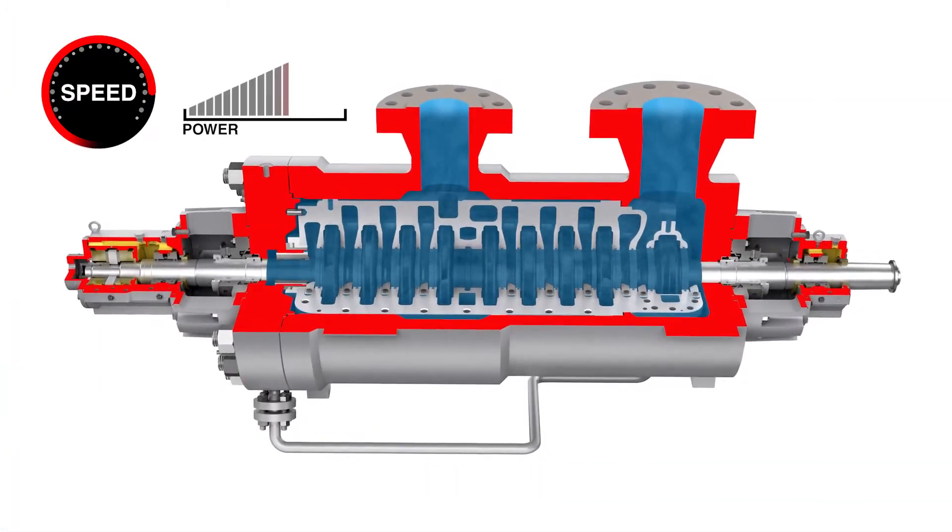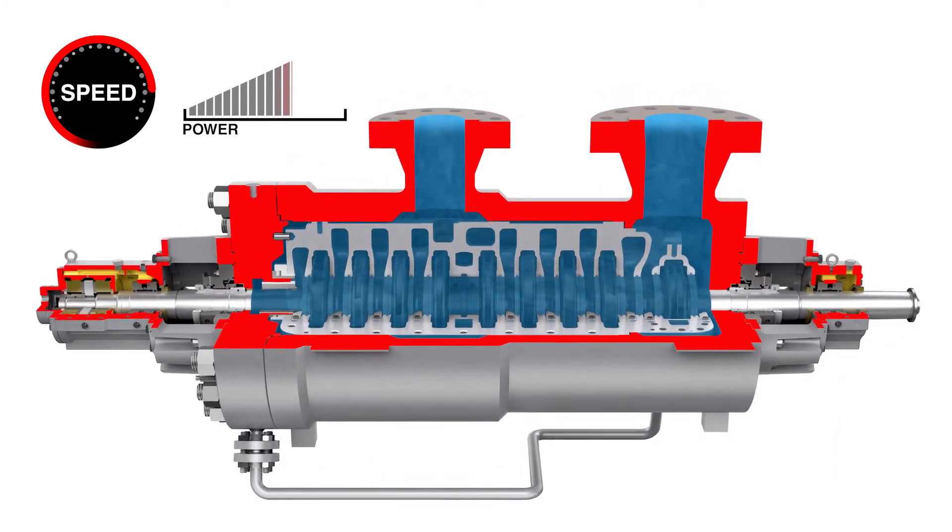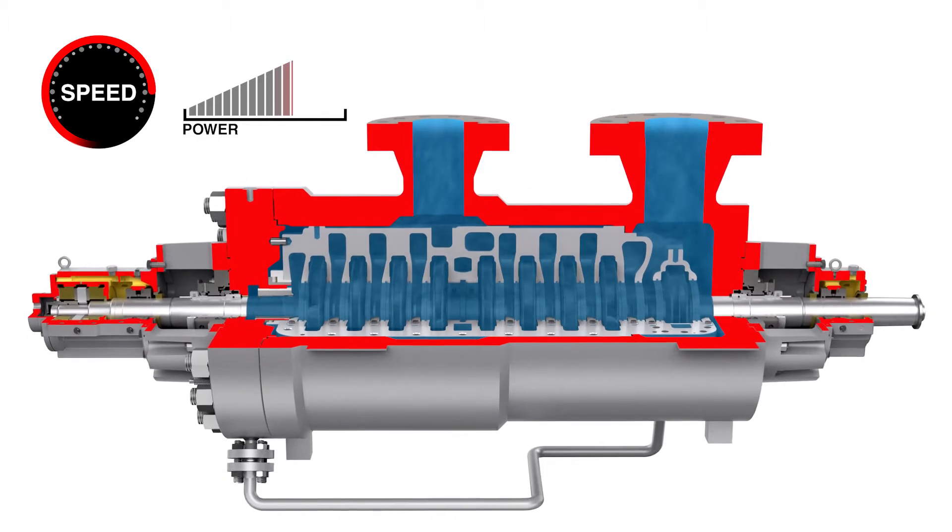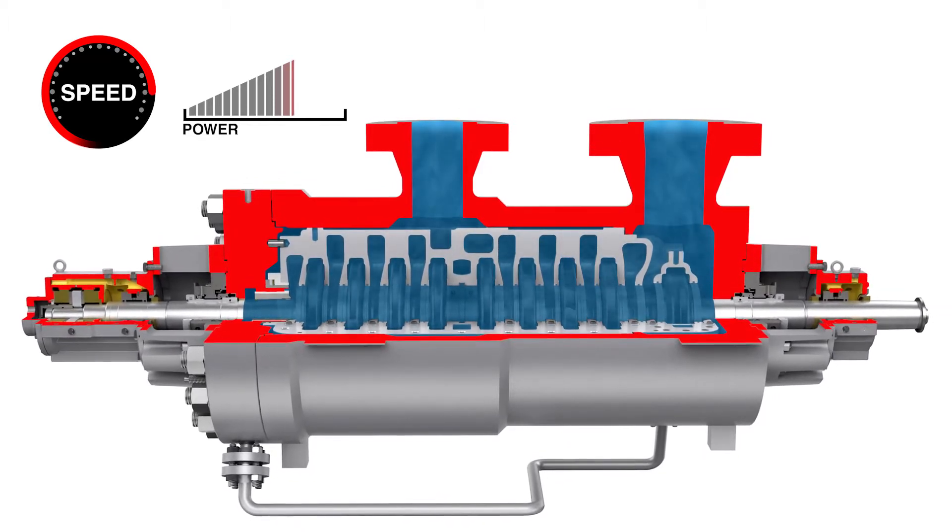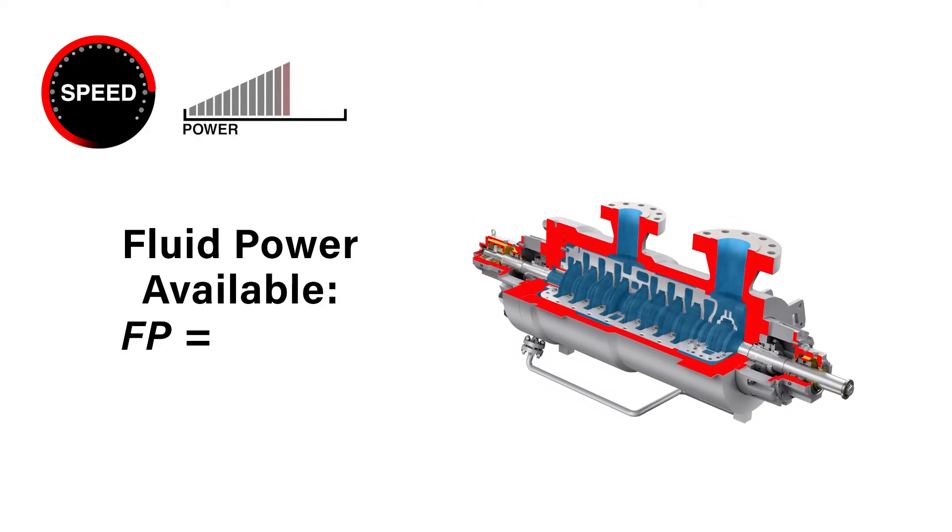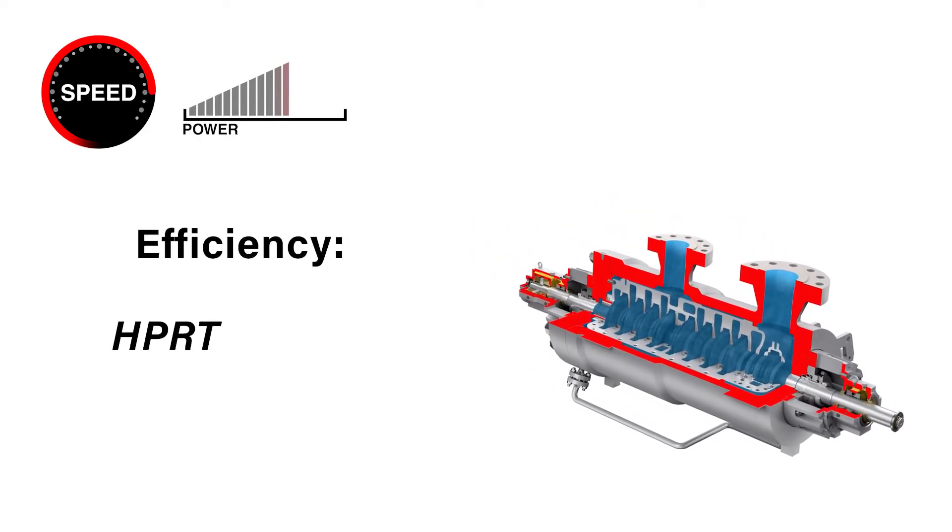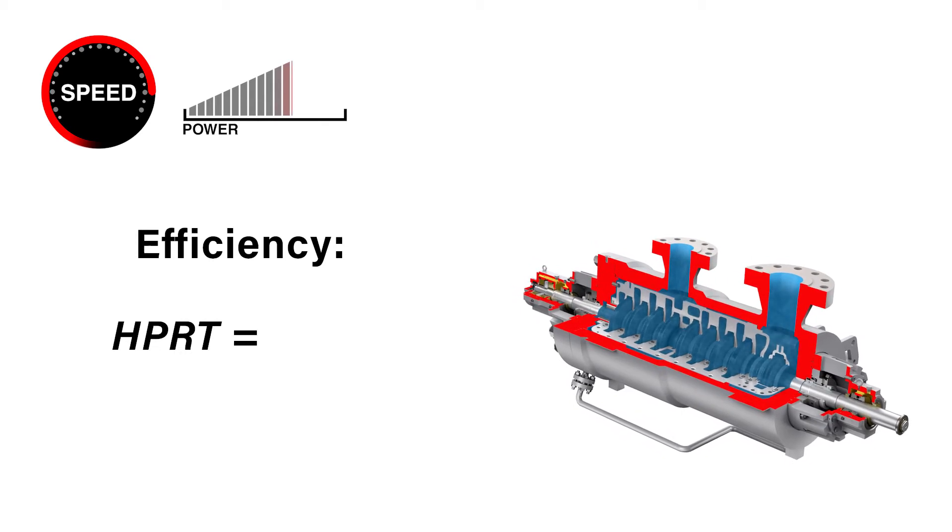To calculate an HPRT's power recovery for a single phase liquid with no evolved gas, we can use a calculation based solely on the inlet capacity and turbine pressure drop. Fluid power available is the product of mass flow, head drop, and gravity. HPRT efficiency is calculated using actual tested power output divided by the calculated fluid power available.